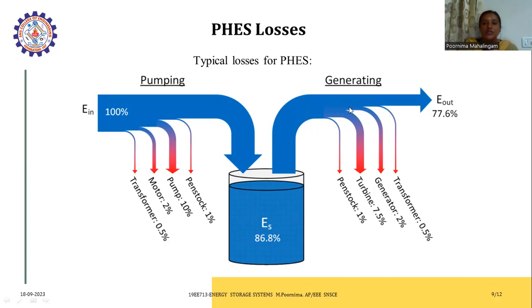Now for generating. In generating mode, we end up getting 77.6 percent. The penstock loss is 1 percent, turbine loss is 7.5 percent, generator loss is 2 percent, and finally transformer loss is 0.5 percent. These are the total losses in pumped hydro energy storage systems.